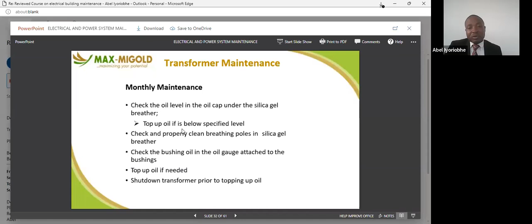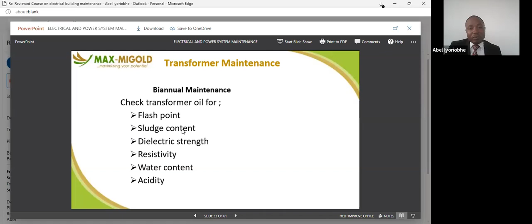We have the biannual maintenance. We check the flash point, the sludge content, dielectric strength, resistivity, water content, acidity, etc. That's what we do biannually.